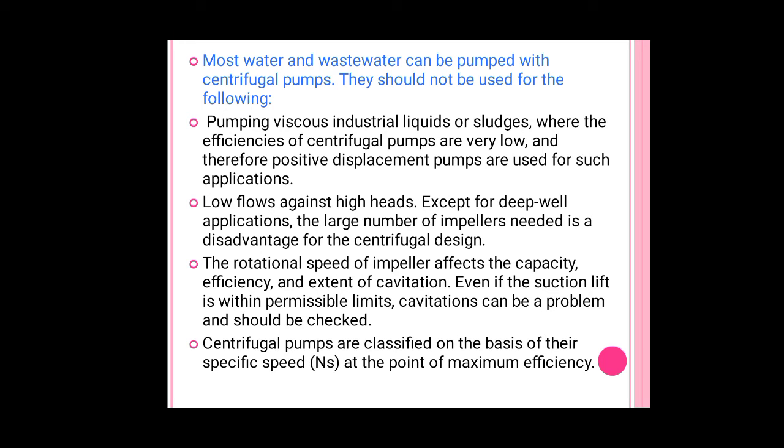In the second condition, low flows against high heads. Except for deep well applications, a large number of impellers is needed, which is a disadvantage for centrifugal designs. Next, the rotational speed of the impeller affects the capacity, efficiency and extent of cavitation. Even if the suction lift is within a permissible limit, cavitation can cause problems and should be checked.